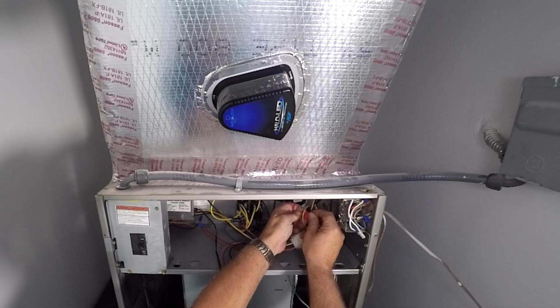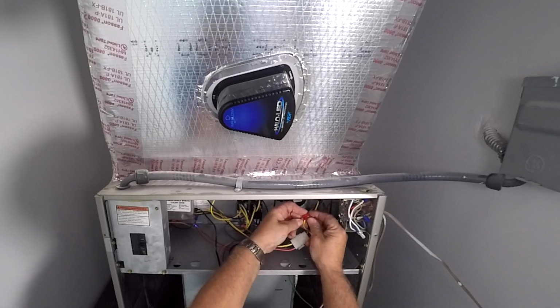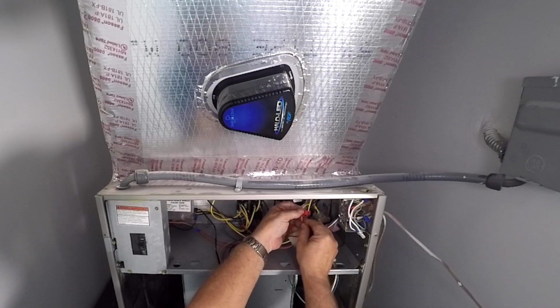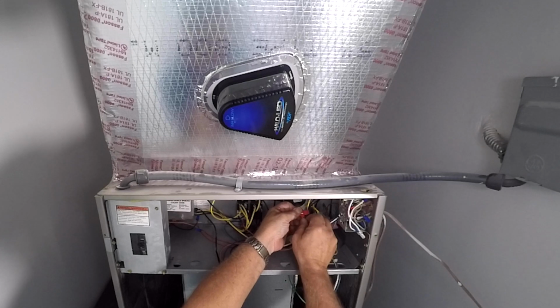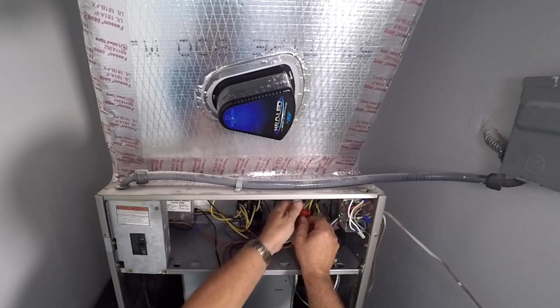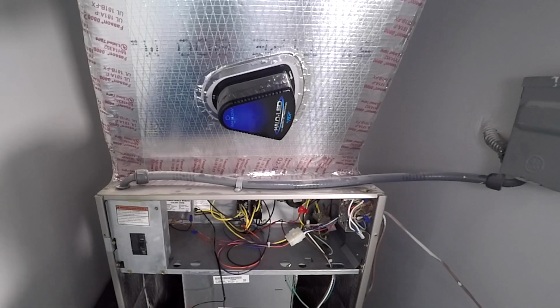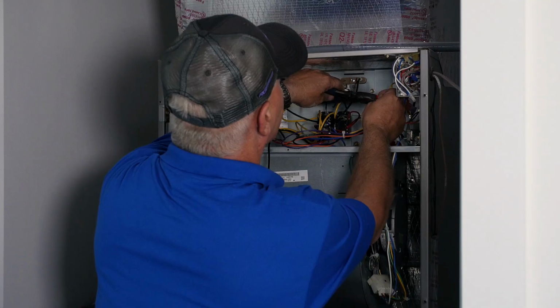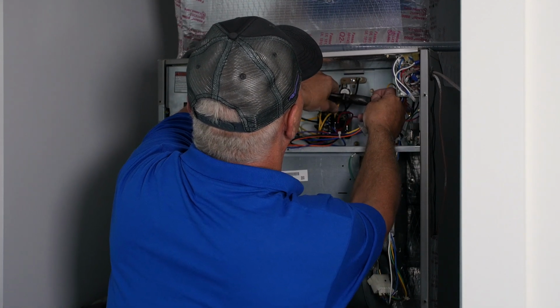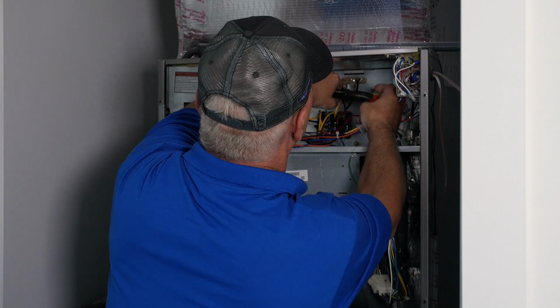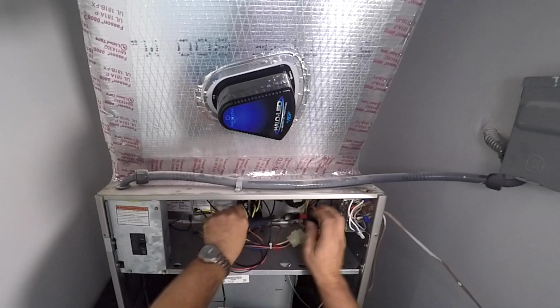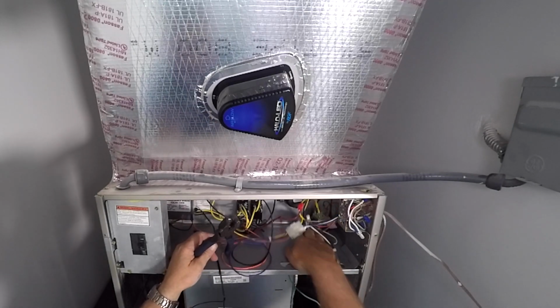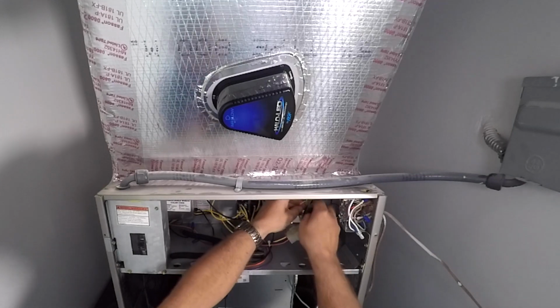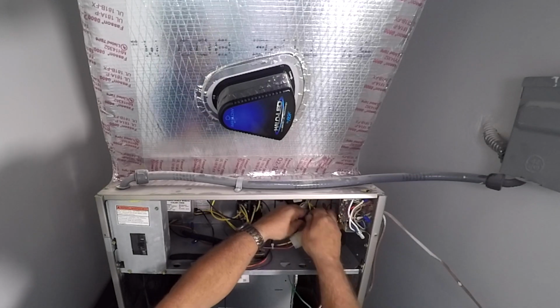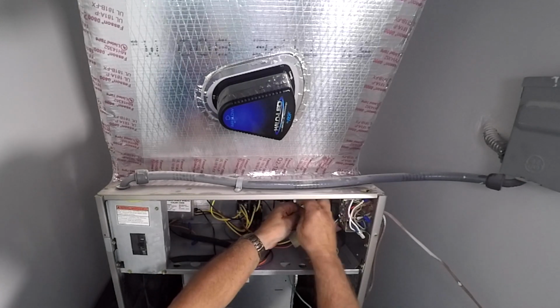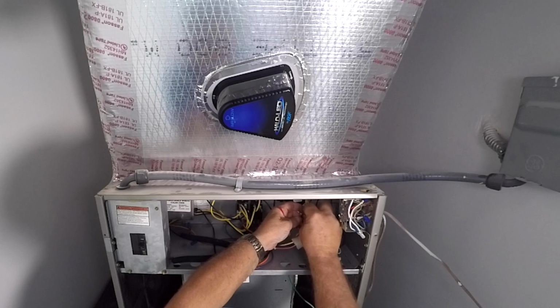I'm using line tap units, which simply snap onto the wires for the feed, and then you just slide your wiring in and, using a pair of pliers, clamp the unit, and it connects to both sides of the wiring. And then you simply snap the top over. So we're going to do that on both the black and the yellow, which is going to feed our low voltage transformer a constant 240 volts, which is going to power the transformer all of the time.